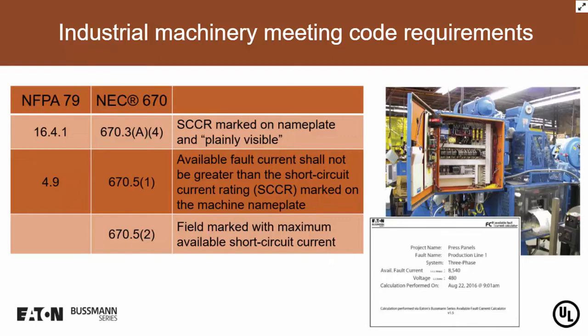That requirement also includes a need for marking the date at which the calculation is made to determine what the available short-circuit current is. That date is important because changes could occur in the electrical infrastructure of the machinery, or in the facility itself, either inside or outside the facility where, for example, the utility might make some changes to the equipment that they're using to supply a building. And of course, that could easily affect the available short circuit current. So that's why the date certainly is important.